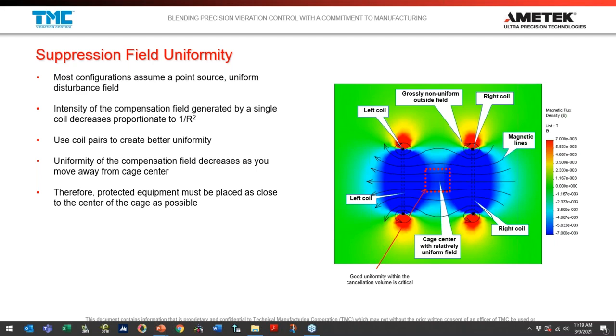In the simplest examples of Helmholtz-type cancellation systems, we assume the field we're trying to cancel is from a point source far away — decayed to the point where it can be assumed relatively uniform. Magnetic fields are always going to vary over distance approximately proportionate to 1/r², so the further you get from your source, the less rapid the drop-off of magnitude — we call that a gradient. Eventually, it becomes asymptotic where it's relatively uniform over distance.